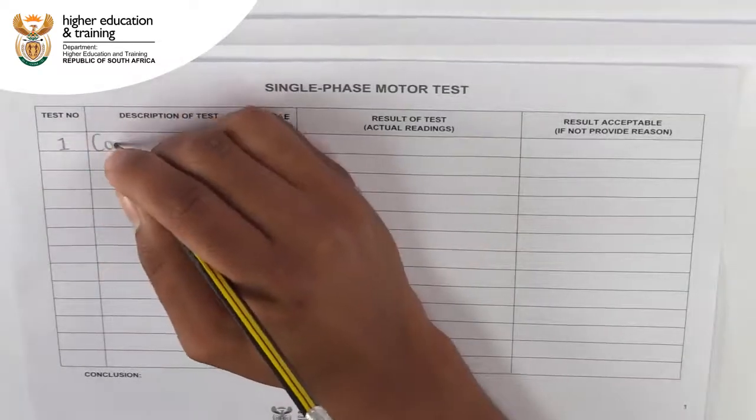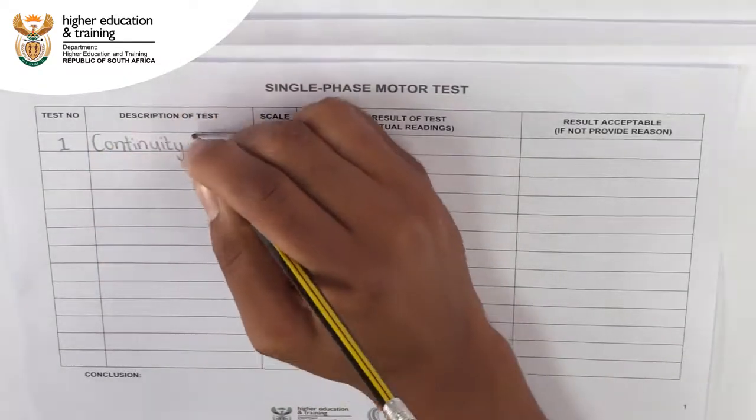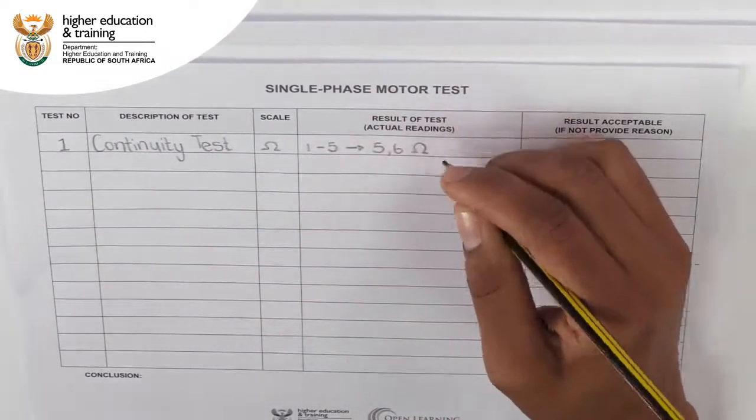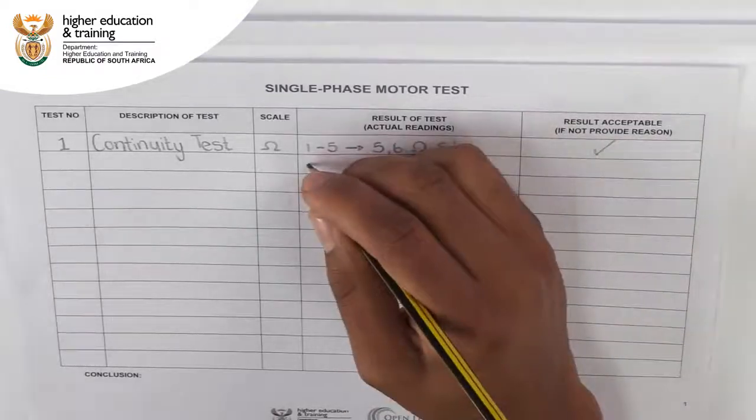We can now fill the results of our continuity tests in on a Motor Test form. Everything is as we expect it to be, so we can mark each test as pass or acceptable.